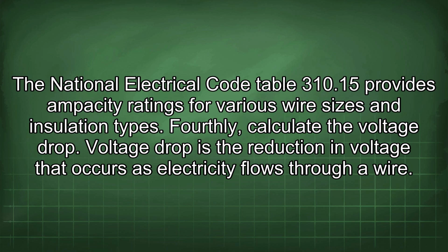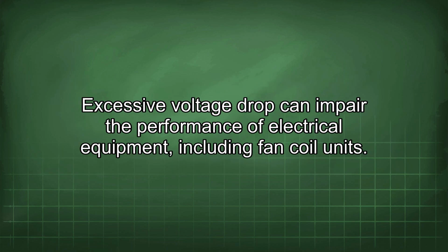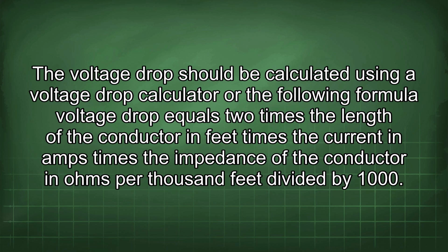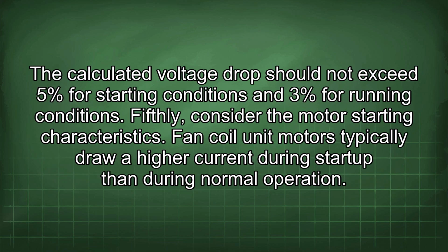Fourthly, calculate the voltage drop. Voltage drop is the reduction in voltage that occurs as electricity flows through a wire. Excessive voltage drop can impair the performance of electrical equipment, including fan coil units. The voltage drop should be calculated using a voltage drop calculator or the following formula. Voltage drop equals 2 times the length of the conductor in feet times the current in amps times the impedance of the conductor in ohms per 1,000 feet divided by 1,000. The calculated voltage drop should not exceed 5% for starting conditions and 3% for running conditions.